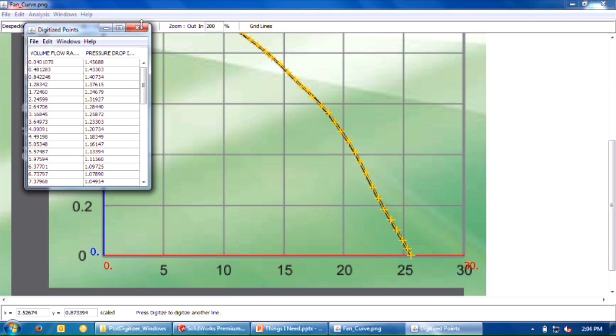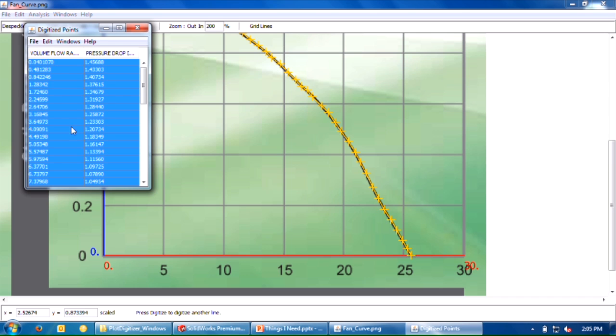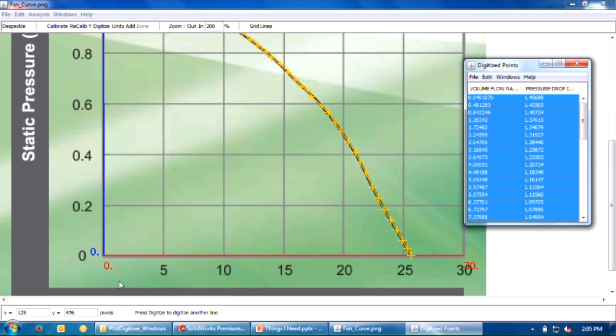You'll get all of those points in columns, in X,Y data. At this point, I can select all or control A and copy paste this directly into flow simulation. But oftentimes the units aren't quite right. I know this plot is CFM in X and inches of water in Y. Flow simulation, depending on the unit system you're using—I'm using CFM and PSI—so I need to do a unit conversion here.